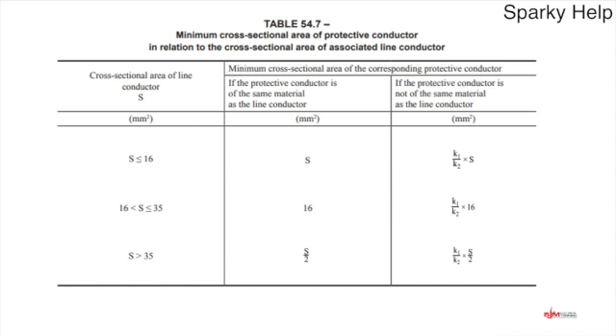If we look at this, it says S is less than or equal to 16 mil. So what does that basically mean? It means cables from 1 mil up to 16 mil. So if you know your cable sizes, that's 1, 1.5, 2.5, 4, 6, 10 and 16 mil. The next one down says greater than 16 and up to 35, so there's only 2 cable sizes in that range. Why they don't just write it, I don't know, but they don't. So it is 25 and 35 mil as our standard cables. The very bottom one is any cable size that is bigger than 35 mil.